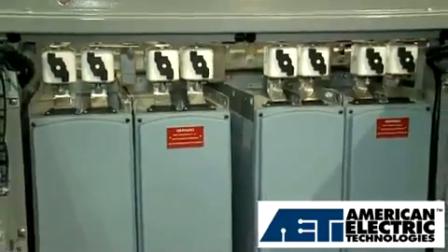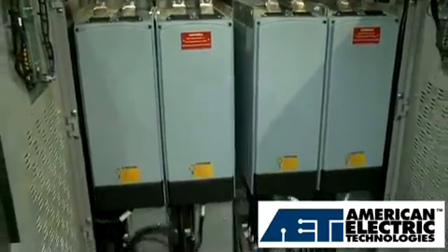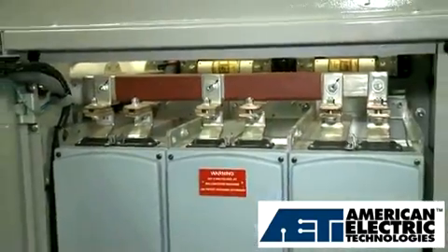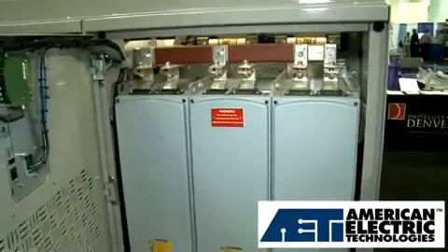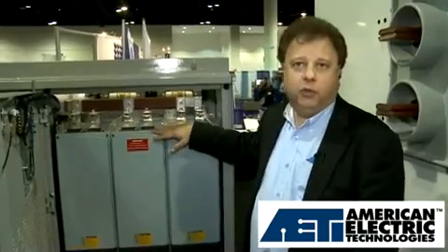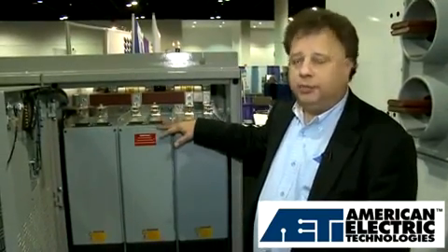But here's what we call the front end of the converter before it goes to the grid tie output. So this is now what we call the grid tie section of the wind converter. It's connected through a DC link over to the two front end machines, and out of the 0 to 10 hertz input comes 60 hertz output at 1 megawatt to a 480 volt grid. As you can notice, it's a very narrow package through and through. It's meant to go through the door.